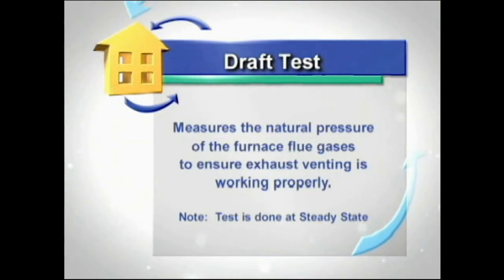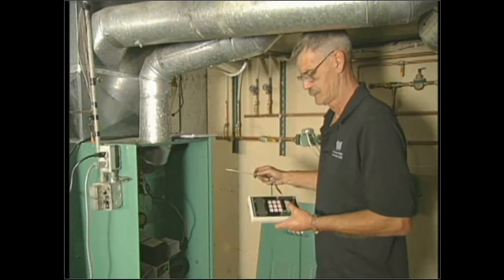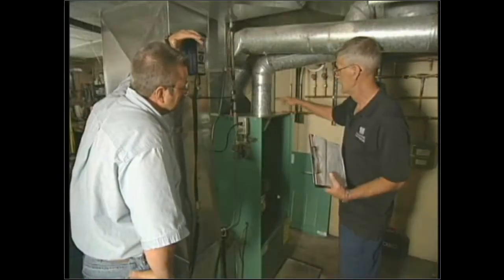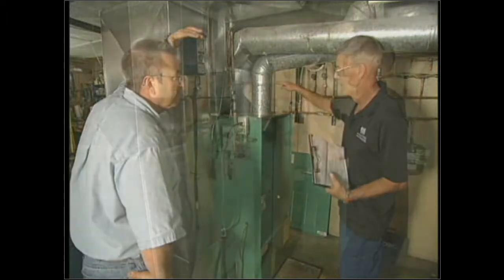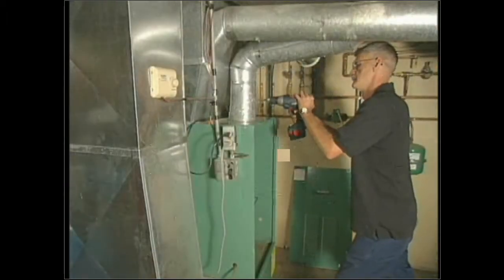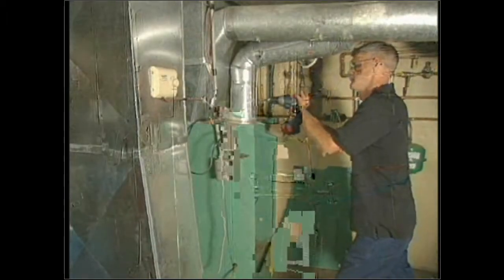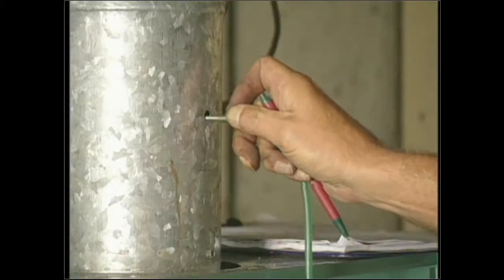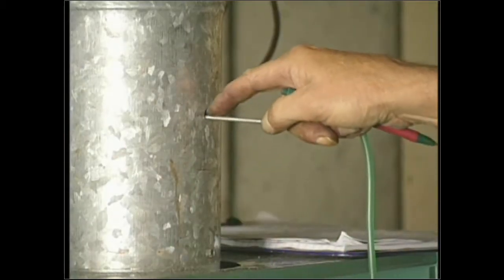So it takes a couple more minutes for everything to warm up. Sure. Then what I will do is take my manometer and my probe. I'll pick a point between here and the first elbow, probably midway, drill a hole. And I'll take my probe, stick it in, bring it back so I got the center. And the reason I want the center is that's the hottest point, and that's where the true draft is.